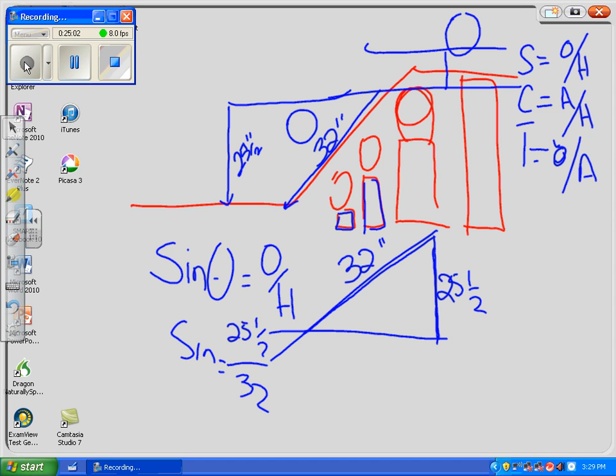And it says, what, 52? That's over 45, but I have to. It's where I can get in. Right? So it's 52.83 degrees. So if I put my marks 32 inches apart and bend it 52 and almost 53 degrees, wait a minute, I've got room to spare on the top, right? I'm going to bend it 53 and 53.